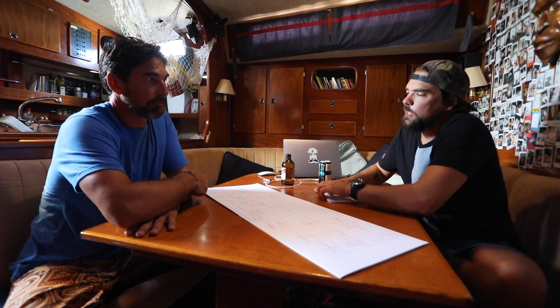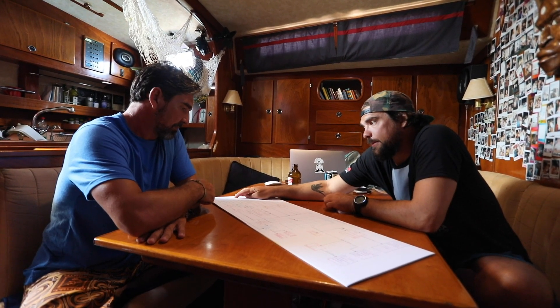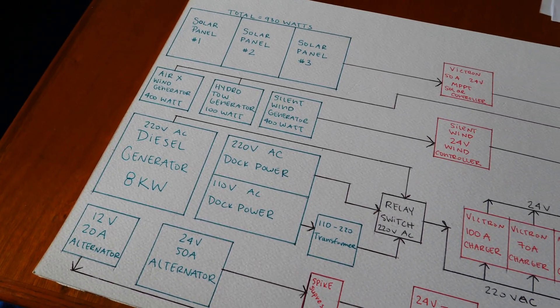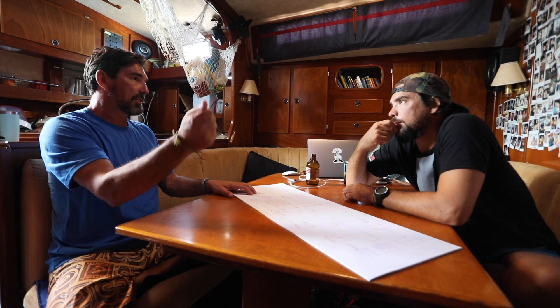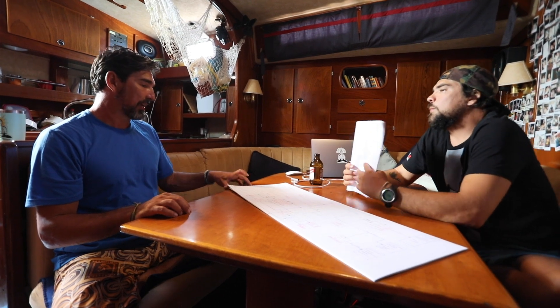With this specific system, let's say you were plugged into dock power, everything was going well with charging, and you then turned the generator on at the same time — what would happen? It would go to the same relay. This relay is a single-selecting relay switch with priorities. The generator takes priority over dock power, so it would switch at that point — the relay sees voltage coming from the generator and disconnects the dock input. If it were the other way around — generator running and you plug dock power in — nothing would happen, because it's already on its priority source. You never want to connect the generator to dock power simultaneously, because as it's AC, if they weren't 100% in sync, it would be a disaster.